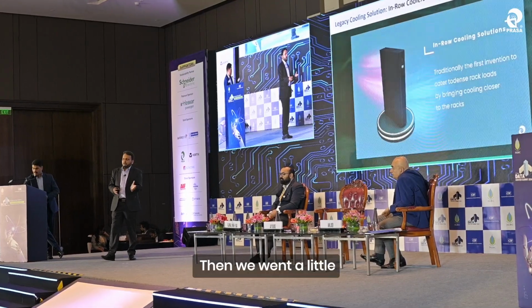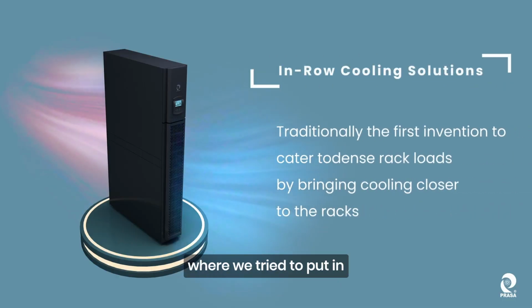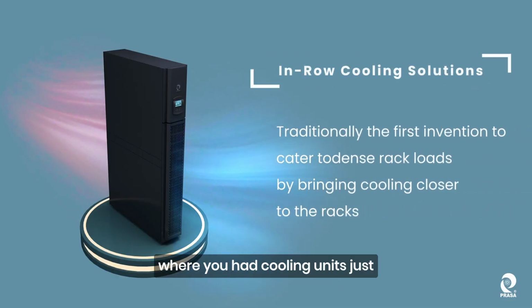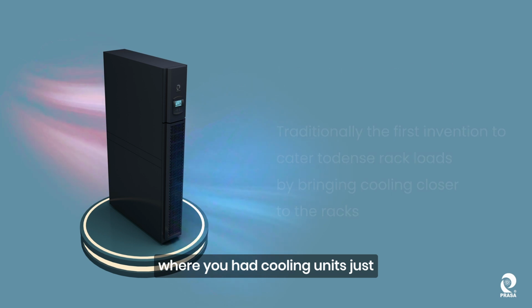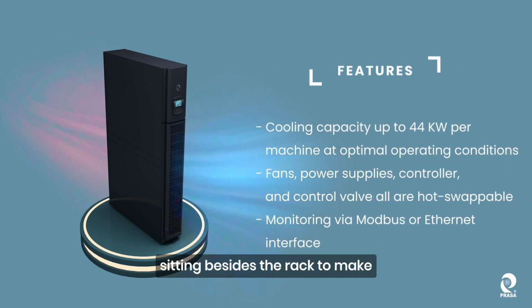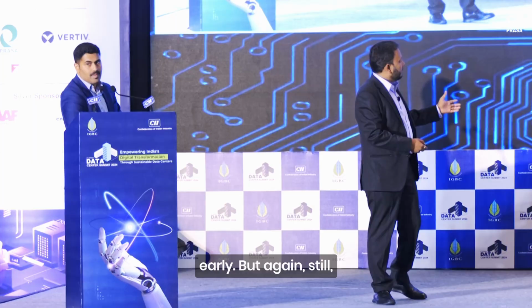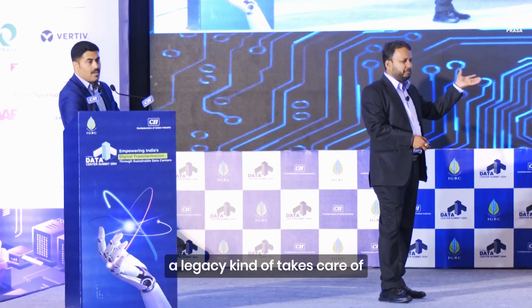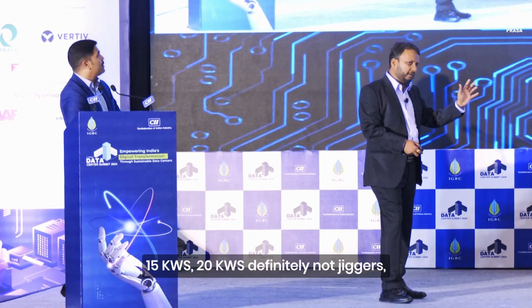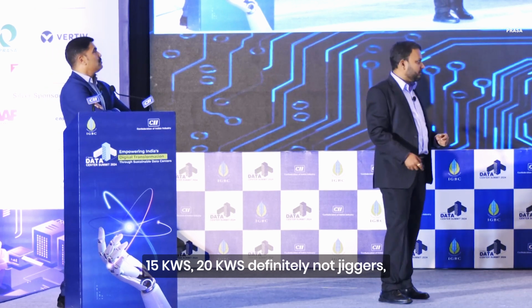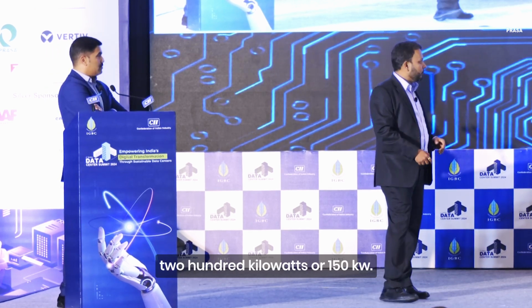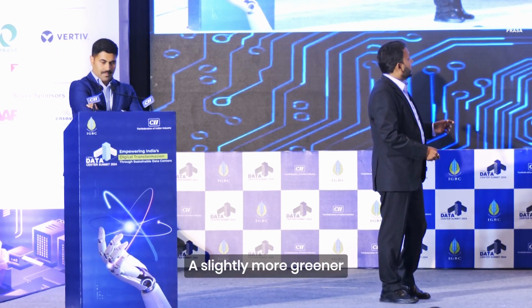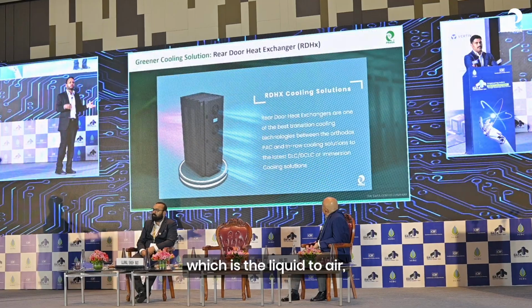Then we went a little denser where we tried to put in in-row units, where you had a cooling unit sitting beside the rack to make sure the air reaches the rack earlier. But again, that's still a legacy solution that takes care of 15 kilowatts, 20 kilowatts, definitely not 200 kilowatts or 150 kilowatts. A slightly greener solution we can call, for now, is liquid to air.